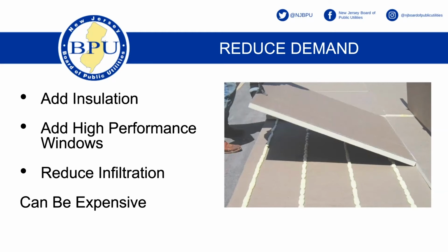Reducing infiltration, that's a lot more than you think. It's subtle. Has anybody ever had a blower door test done in their building? What did it tell you? They couldn't even do it. They didn't bring enough blowers. Because there were so many holes. Oh, my. Yeah, amazing, right?